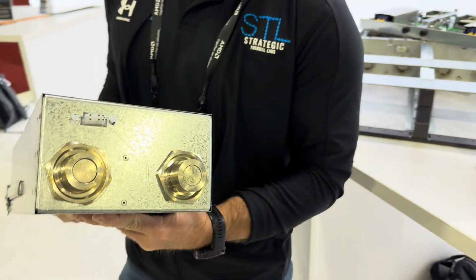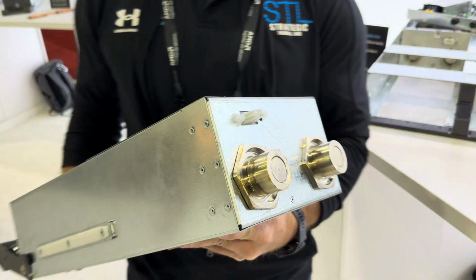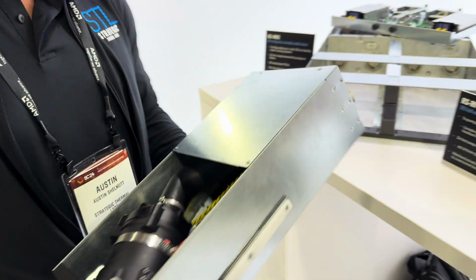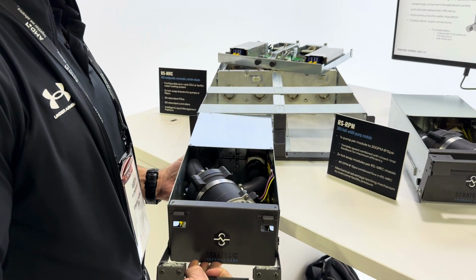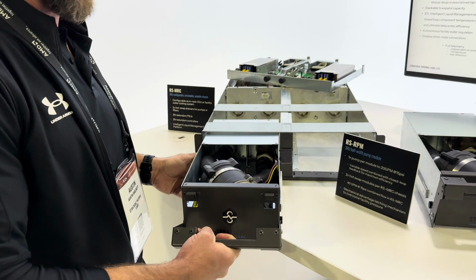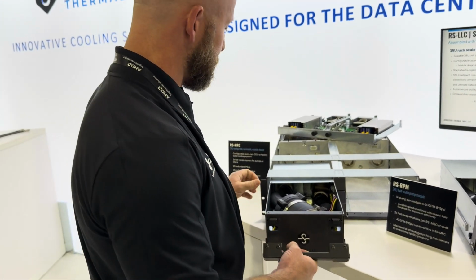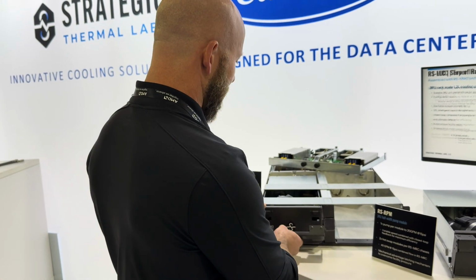They have dripless quick disconnects in the back of the tray, along with a power cable and leak sense wire. The pumps we use are PWM controlled, so we can vary the speed of the pump dynamically based upon demand in real time. And then the pump cord goes back into the enclosure.